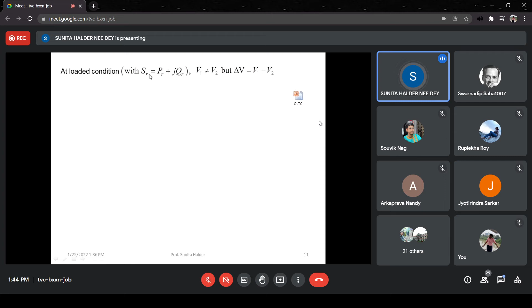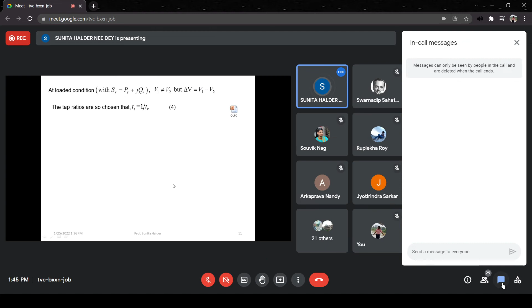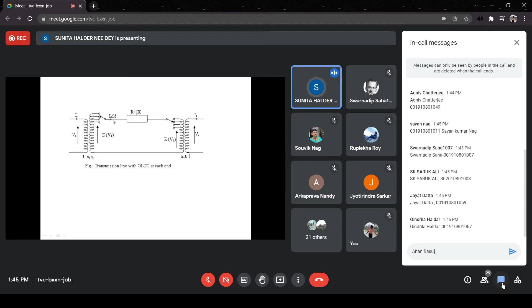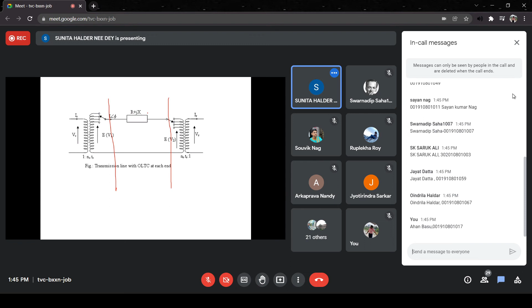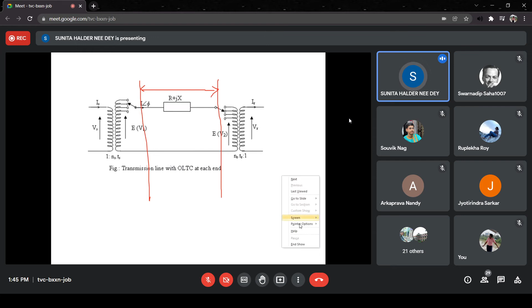Now say at a loaded condition, when there is a load at the receiving end, in that case V1 will not be equal to V2, some current will flow through the transmission line, so delta V equals V1 minus V2. Now taps are always chosen in a reciprocal way. In the power transmission system, this is required, otherwise we cannot maintain the voltage. So now what will be the voltage drop? If you forget about the transformers, then this part is only a short transmission line. Then what will be the voltage drop through it? IR cos phi r plus IX sin phi r.